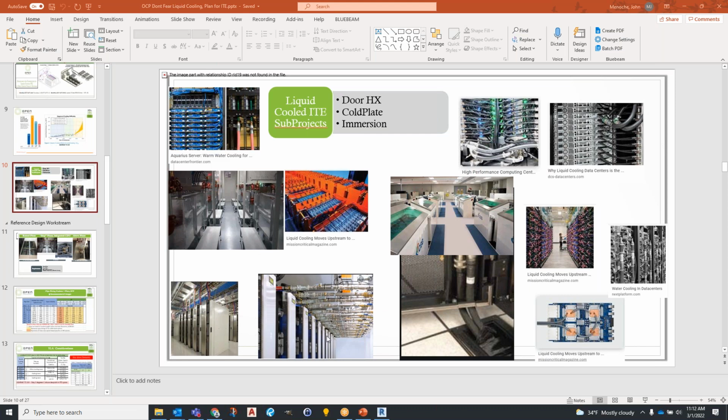Excellent. To put a bit of a view onto what John was just mentioning, this is a liquid cooled rack solution here. You can see the supply and return piping is running in front, basically level with or just a little bit above the top of those racks. I'm not familiar with this installation, maybe Don can shed some light, but it looks like you wouldn't be able to easily get on the top of these racks from here. So to John's point, if your cabling is running in a cable tray along the tops of the racks, something like this in the front might be a problem, right?